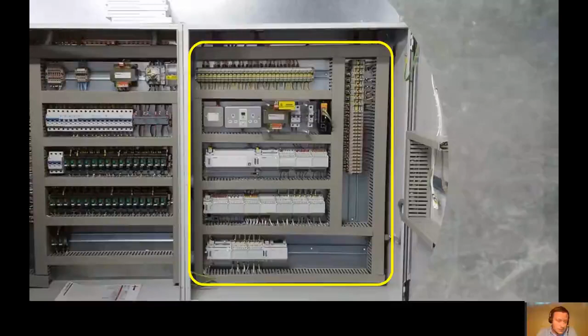So typically what manufacturers do is we'll provide a 2-form panel or 3-form or even 4, whereby we keep the extra low voltage stuff separated from the higher power stuff. So the low voltage, I think, is 50 volts up to 1,000 volts, and extra low voltage is anything 50 volts and below. So really, to try and insulate the power is where we're trying to get that across.